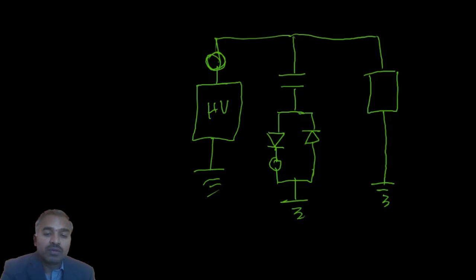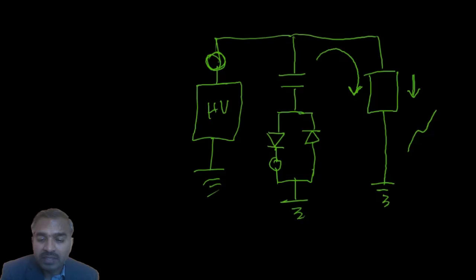Now what will happen is, through this path, as the voltage is increasing, inside the test object there may be certain discharges. That will cause the voltage to dip. Although you may be supplying a pure sinusoidal voltage, that will cause the voltage to dip like this. It may be possible.